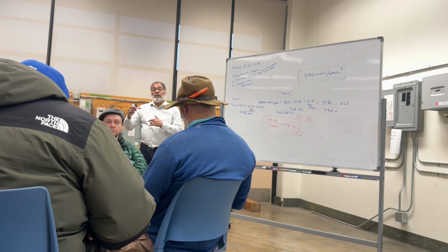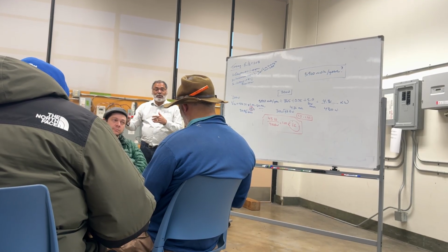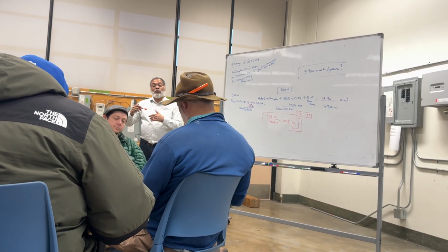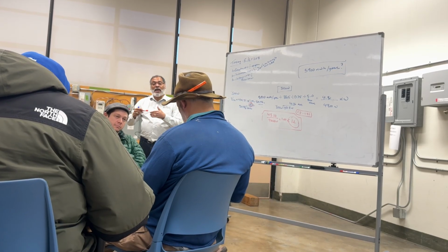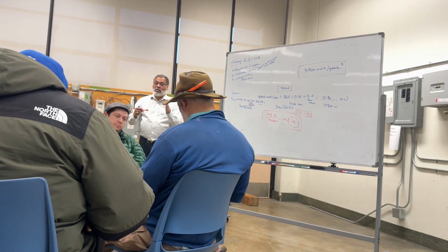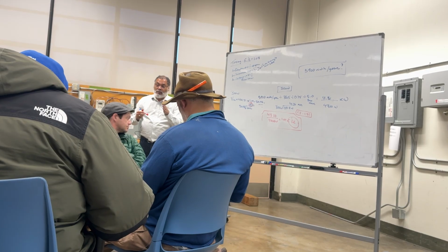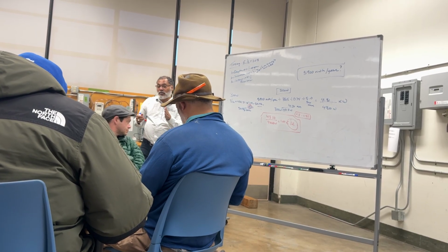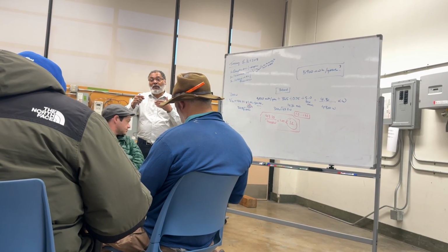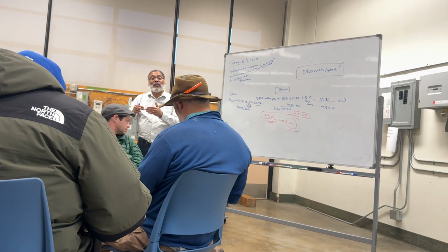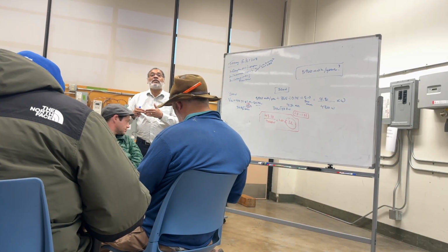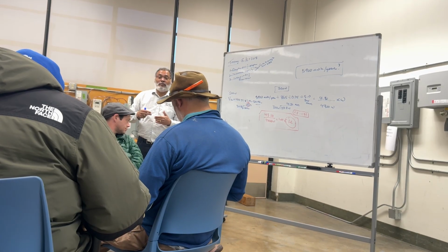Or yes, but no, maybe that's the right way of putting it: if you're keeping the string length short and then going to another maximum power point track. So you can either keep the same maximum power point track, they both have to be 11, but if you're on a different maximum power point track, they could be different lengths. But I wouldn't suggest anything less than 11.